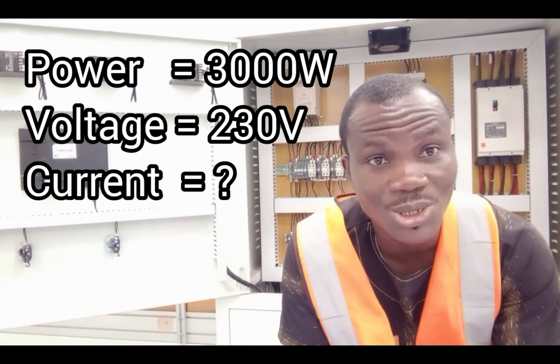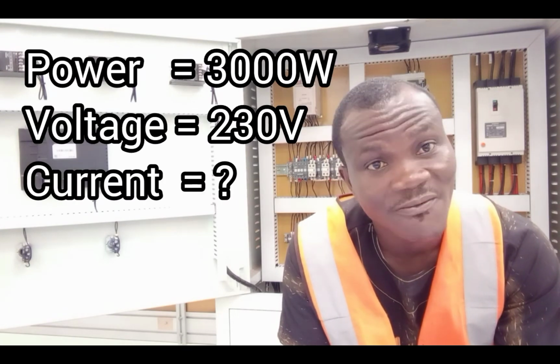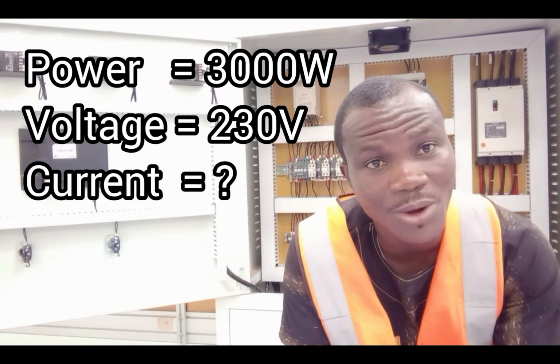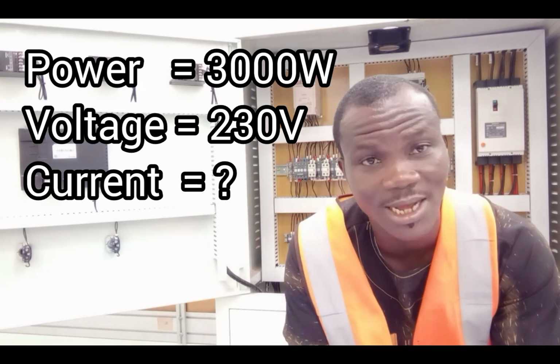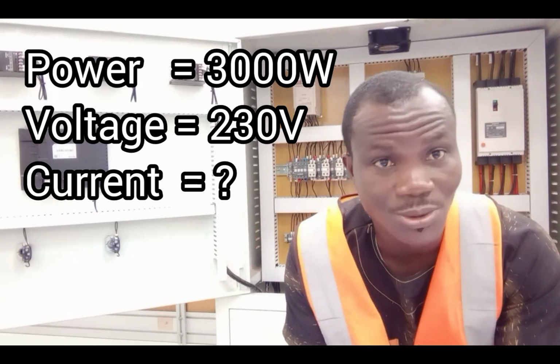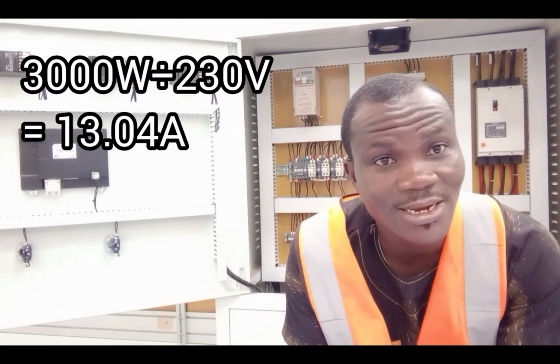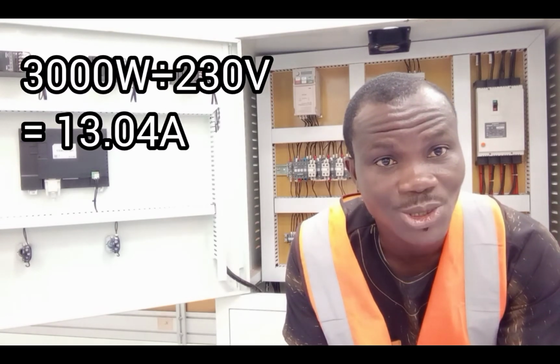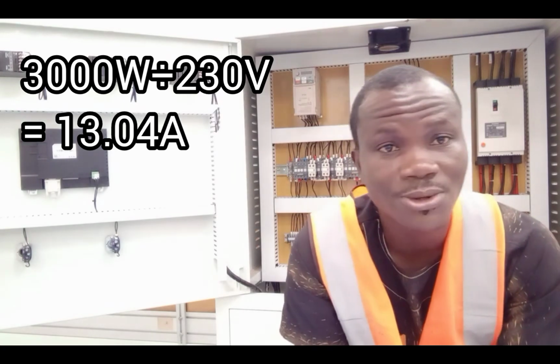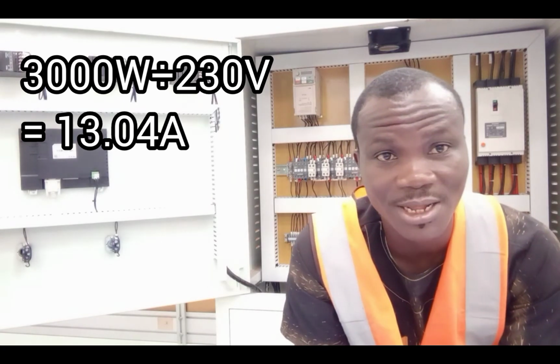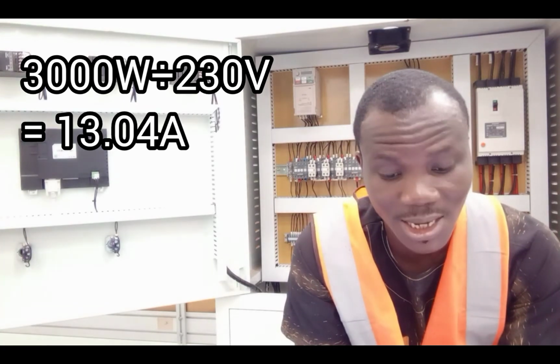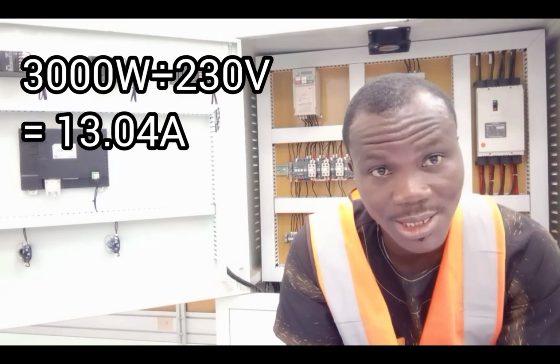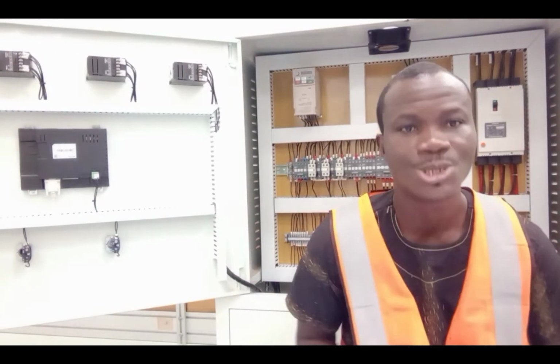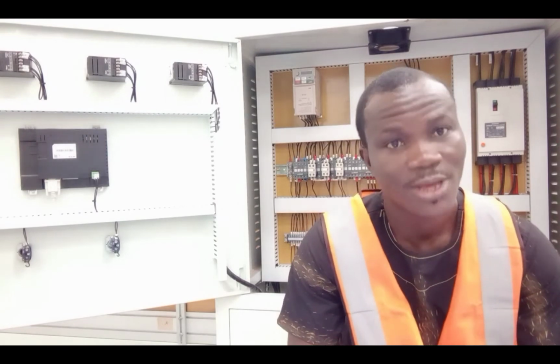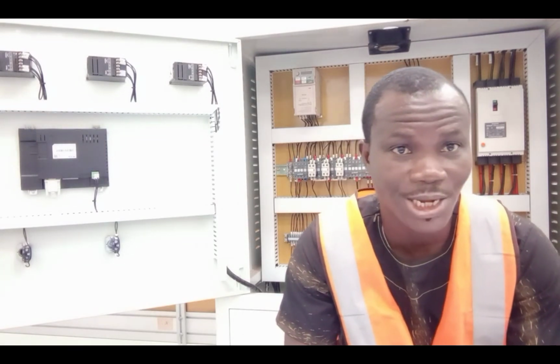All right. So let's assume we have a cooker that consumes 3000 watts. The voltage is constant. So if we want to know the amount of current that this cooker will consume, we divide 3000 by 230 volts. And so 3000 divided by 230 volts gives us 13.04 amps. All right, so now we know the amount of current that our load requires to work.